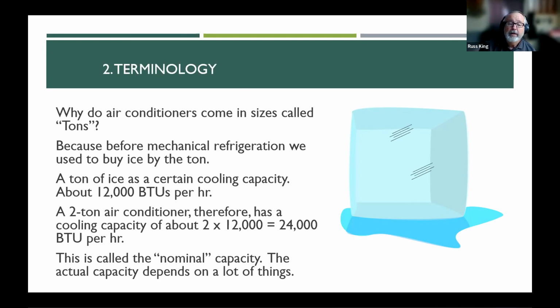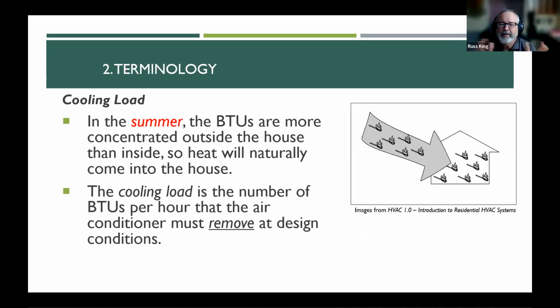But then in order to determine the actual capacity, you have to know the outdoor temperature it's operating at, how much airflow is blowing across the coil, and what the humidity is. Things like that will usually reduce that 12,000 by a certain percent. But when they test the unit, they test it at certain design test conditions. They get close to the nearest 12,000 BTUs, and that's what they call the 4 ton and the 5 ton. I just want to make sure you understand it's a little more complicated than that, but that's fine for normal discussion.